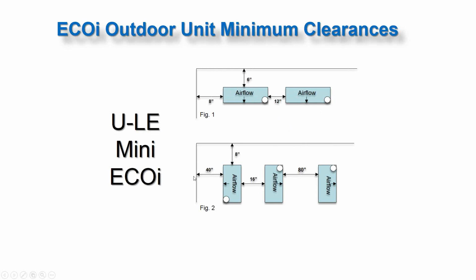If we have air discharging towards a wall, we want to see 40 inches for that. Obviously 8 inches from the side, just like here. If we have 2 units back to back, the coil sides are facing each other, we could do a minimum clearance of 16 inches. If we have a unit discharging into a coil side, so we've got the fan side blowing into the coil side, we want to see a minimum of 80 inches. Anything less than 80 would be problematic. This unit would not heat or cool because it's got this unit blowing into it.